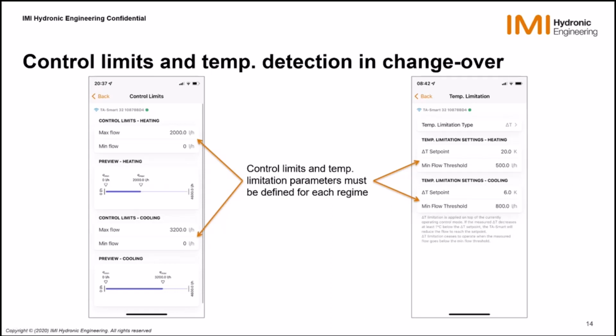Nothing has changed. It is just the fact that when the valve is in heating, then this min flow and max flow will apply, and this delta T set point and minimum flow threshold will apply. And when the valve switches to cooling, then the bottom ones will apply.